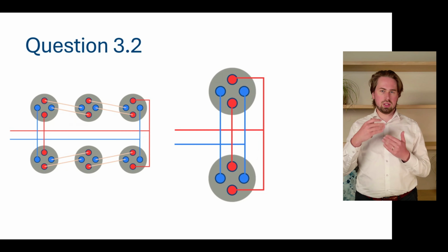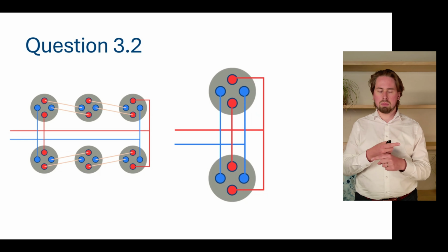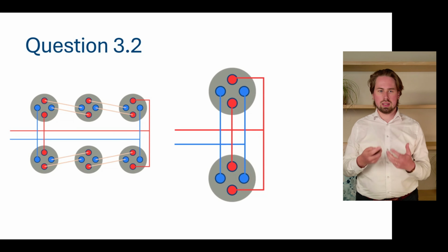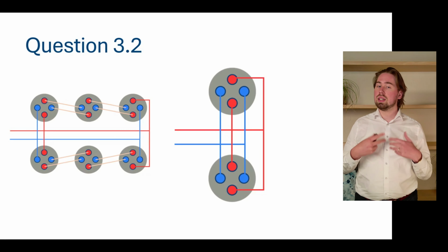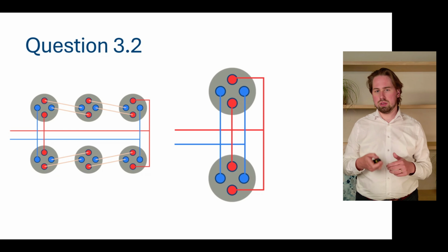The length through each group is the same. And since the flow direction is opposite in each string of connected U's, we can also say, yes, this is indeed a Tichelmann connection because there is no preferential route. No matter the path the fluid selects, it will be the same pressure drop, the same hydraulic length.